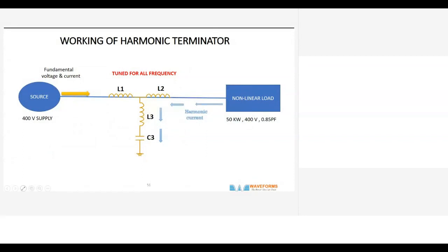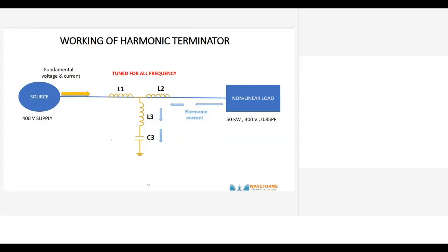So these are 3 windings. I'm just giving a single line diagram. Normally there will be about 9 windings in one structure, but I'm just giving the single line diagram. Okay, so here you have a non-linear load, which can be a drive or something. You will have harmonic currents flowing, and this inductor L2 will limit some of the harmonics, say the 7th harmonic or something like that.